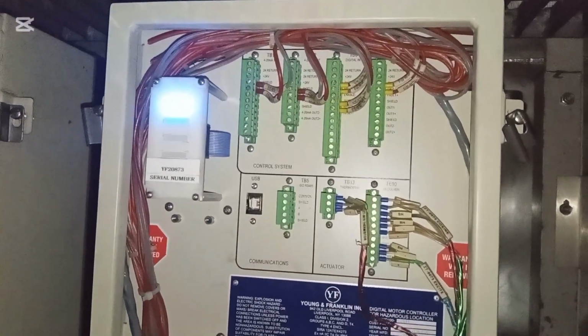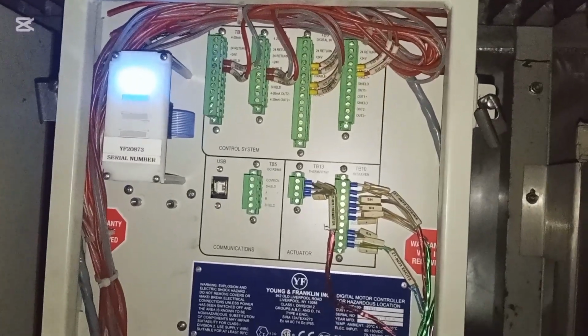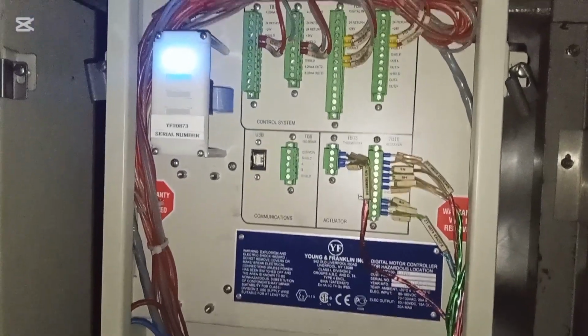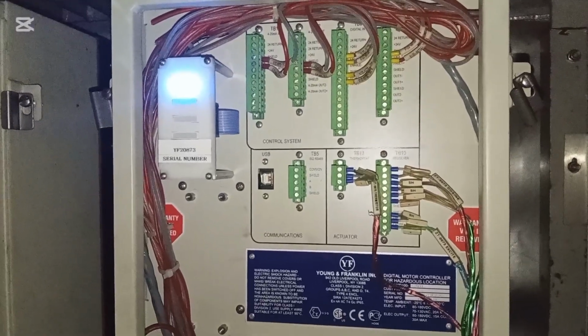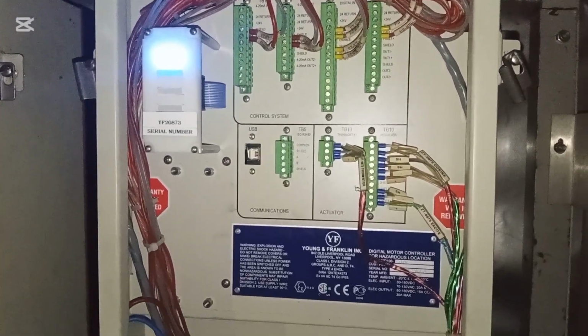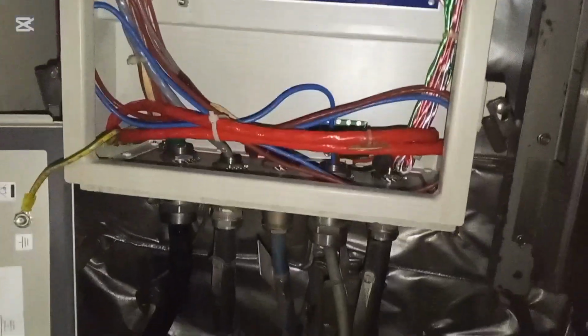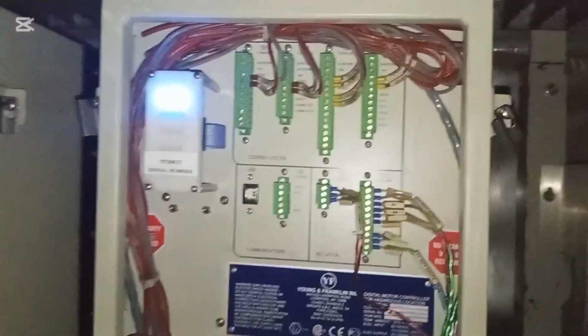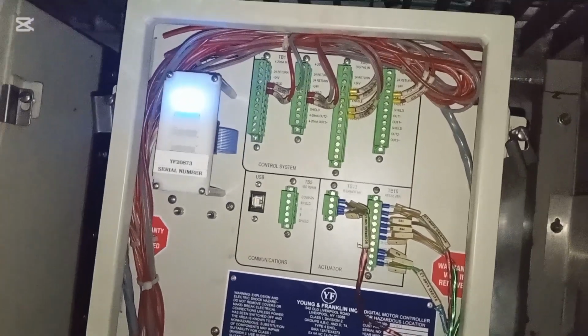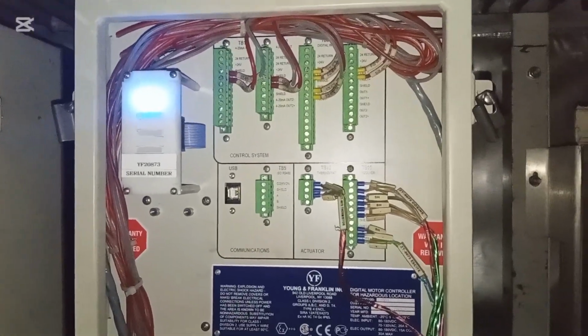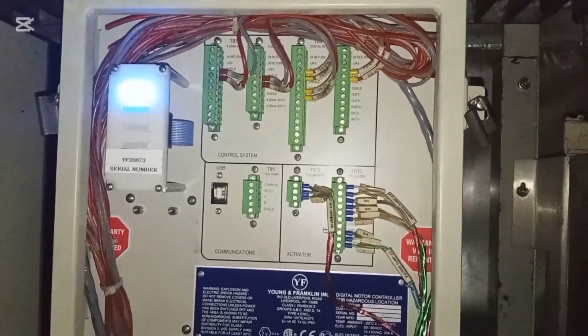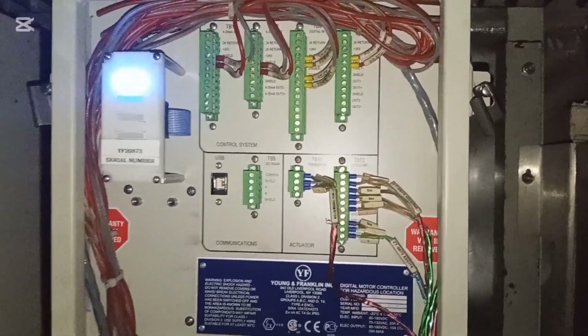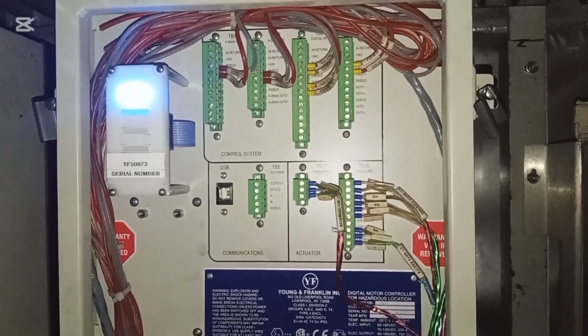This is the first condition, when only one power light is on, and after the reset condition all three signal lights are on. In this way we removed the GE manufactured gas turbine diffusion line valve driver fault problem.